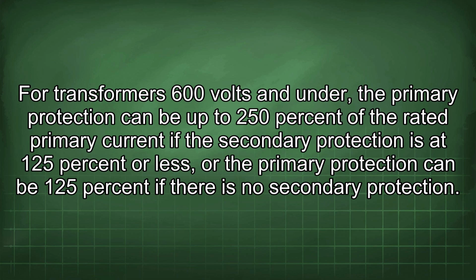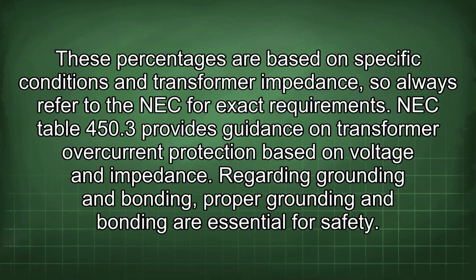For transformers 600 volts and under, the primary protection can be up to 250% of the rated primary current if the secondary protection is at 125% or less, or the primary protection can be 125% if there is no secondary protection. These percentages are based on specific conditions and transformer impedance, so always refer to the NEC for exact requirements. NEC Table 450.3 provides guidance on transformer overcurrent protection based on voltage and impedance.